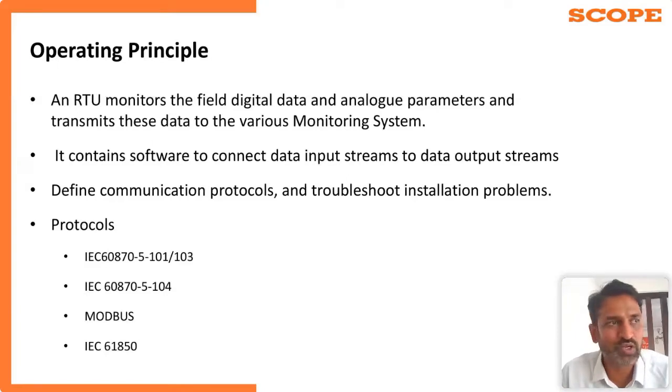One is the Modbus protocol, which is the old protocol. Nowadays we are using it only in meters, MFTs, like multifunction transducers or multifunction meters, MFMs, where we want to take the CTPT data to be connected with the RTU. So we still use Modbus communication.